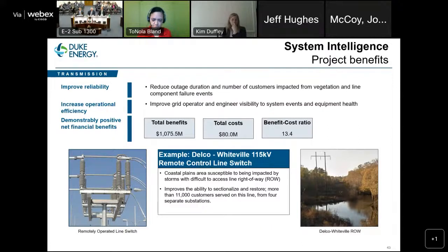Traditionally these switches are manually operated. So once a fault is identified and located, a lineman has to drive to a switch, which could be tens of miles away, open it using a crank handle, and notify the control center so they can restore load using breakers at the substation.